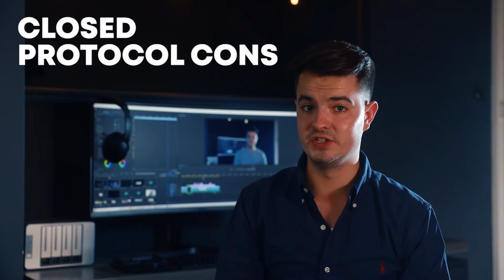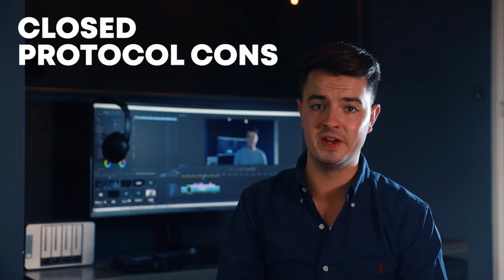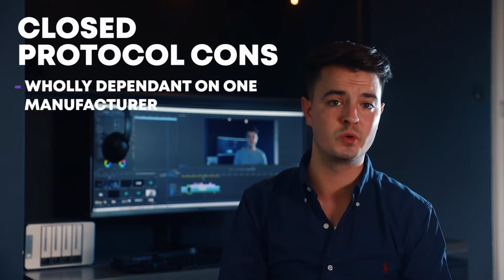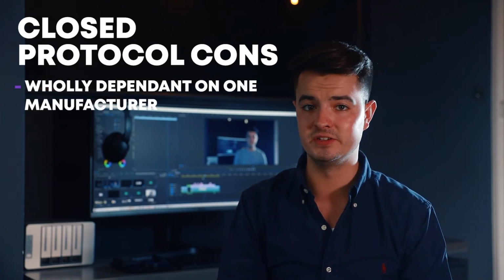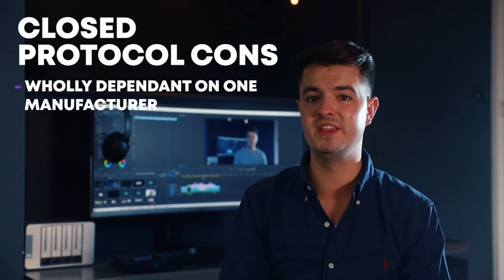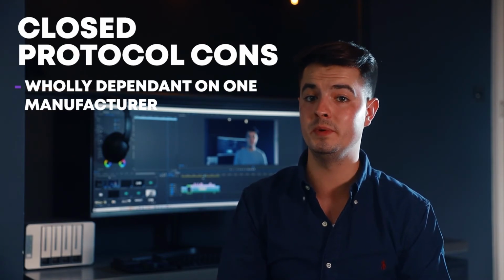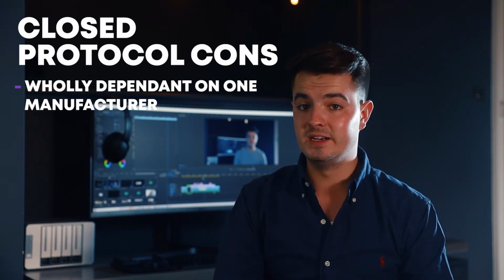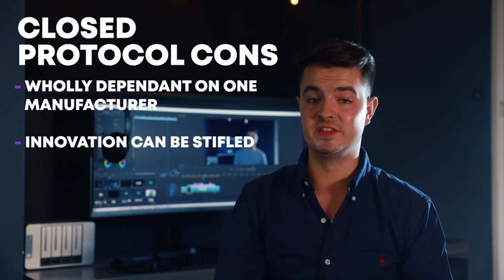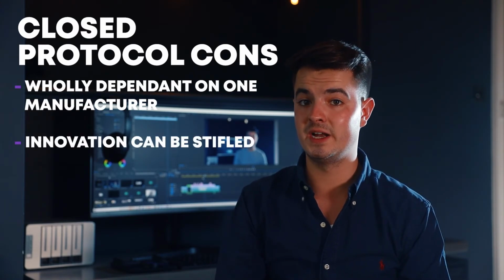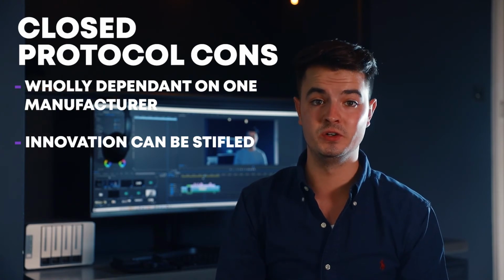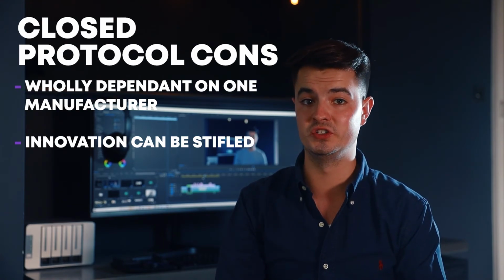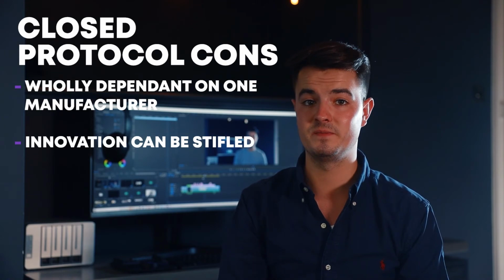As for the disadvantages, firstly, as a building owner, you are wholly dependent on one manufacturer for access to new equipment, upgrades, spares and maintenance. Without direct competition, this tends to allow manufacturers to charge you a premium rate for these services. Secondly, upgrades to the system could be restricted to the technology currently available from the chosen manufacturer or supplier, potentially affecting your choice of brand new or innovative solutions available elsewhere on the marketplace.